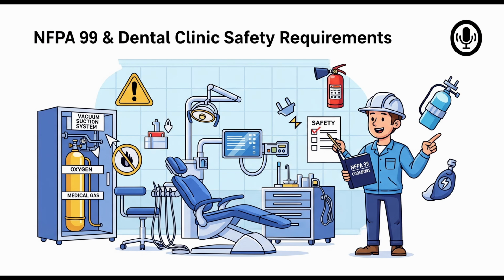Right, I can imagine. Now, you mentioned fire hazards earlier, particularly with oxygen. What can and can't be stored near these gas cylinders? This is probably the most critical storage rule. Oxygen and nitrous oxide are oxidizers. They don't burn themselves, but they make other things burn much more intensely. So Section 11.3.6.6 is strict. No smoking, no open flames, no electrical heating elements, basically no ignition sources allowed within the storage location. If it's an outdoor storage area, that no-ignition-source zone extends out 6.1 meters or 20 feet. There's a 20-foot clear zone outside.